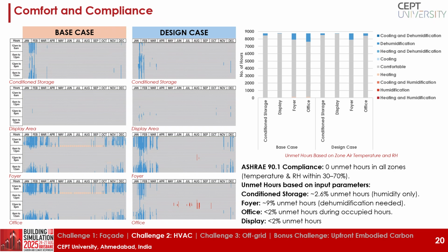Coming to the comfort and compliance, the unmet hours based on ASHRAE standard 90.1 in the design case is 0 hours for all the zones. That is, temperatures meet the set point while the RH is within 30 to 70%. But the unmet hours based on the input parameters for both temperature and humidity limits, condition storage has 2.6% unmet hours and foyer has 9% unmet hours. These many hours require dehumidification alone. For office, considering only the occupied hours, the unmet hours are within 2% and the display area also has less than 2% unmet hours for 8760 hours of the year.